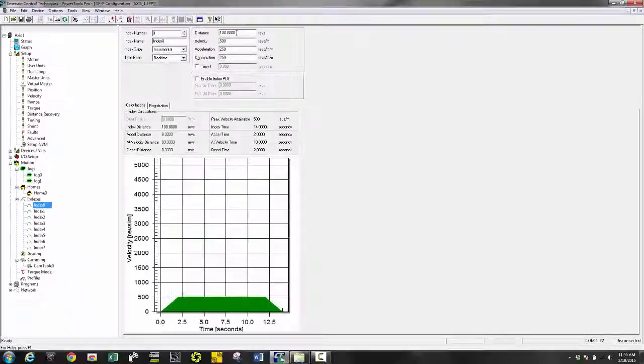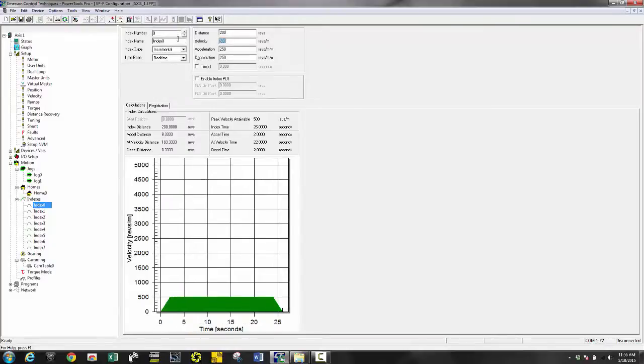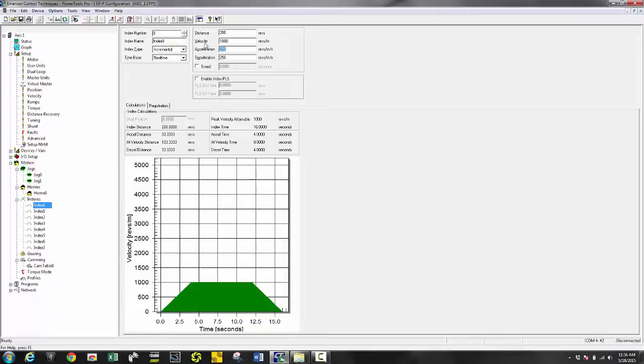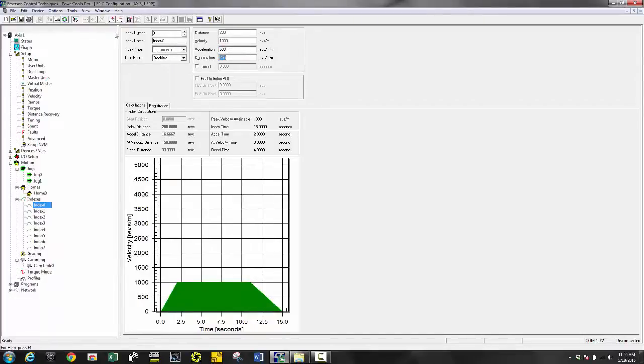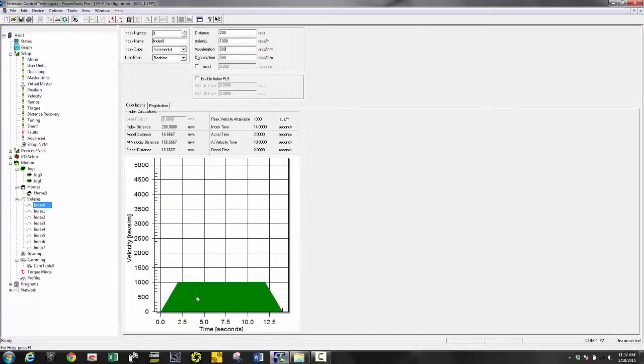Next, I want to set up an index. I'm going to choose an index distance of 200 revs and let's go with a velocity of 1000, with an accel of 500 and decel of 500. One of my favorite features is the graphical representation down below. It shows actually how long it's going to take and how many revs. So it makes it pretty easy to understand without actually having to try to do it.